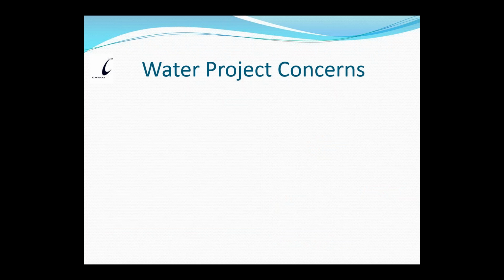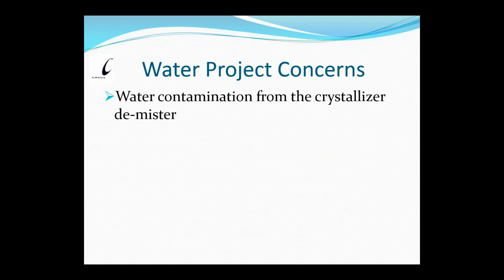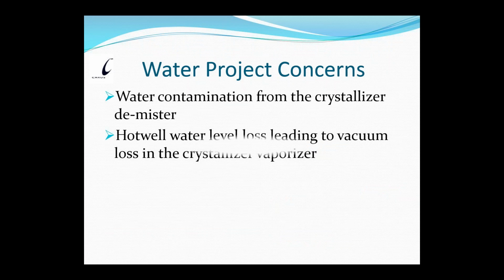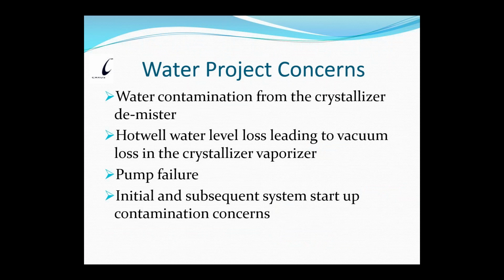Water project concerns. First one was water contamination from the crystallizer demister. We spoke about that. That was the conductivity part, right? Next concern was a hot well water level loss leading to vacuum loss in the crystallizer vaporizer, which is what I had spoken about earlier. Pump failure. Initial and subsequent system startup contamination concerns. Water quality, raw versus recycled.